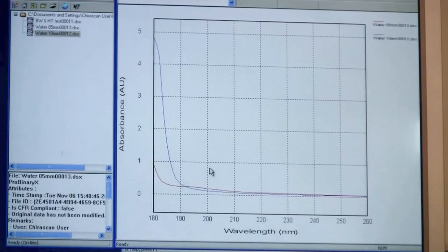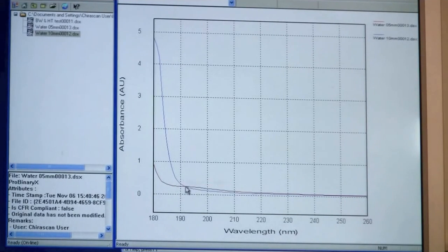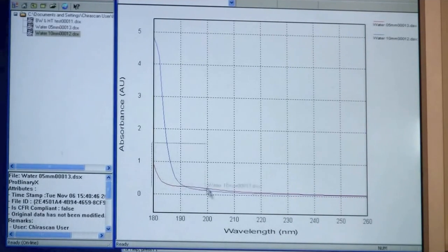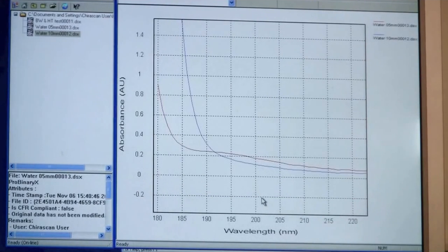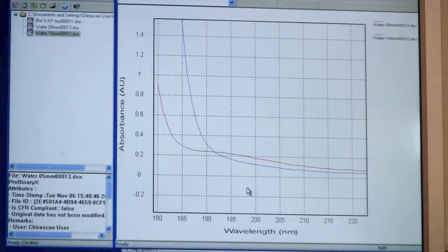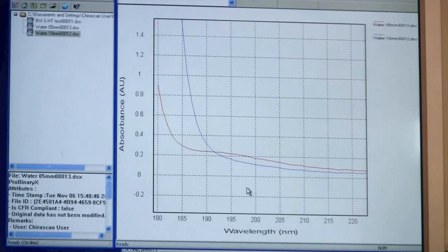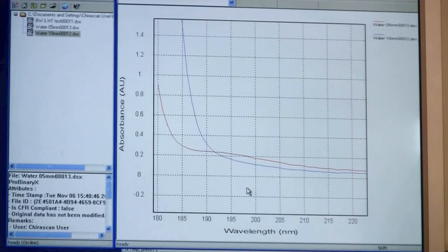The other thing you can notice is that there is a little bump here on the red line. If I zoom in. That indicates that maybe my cuvette is not completely clean. So running water traces can also be used to check if your cuvette is actually clean or not.